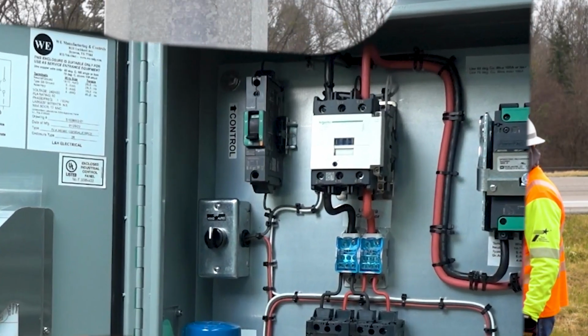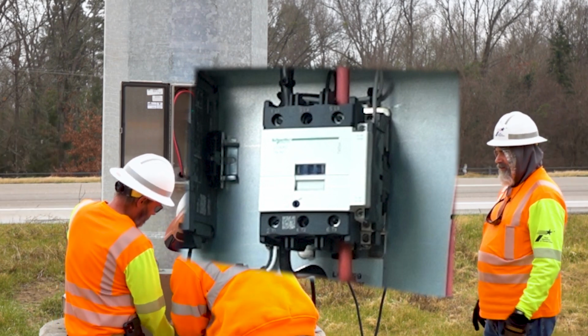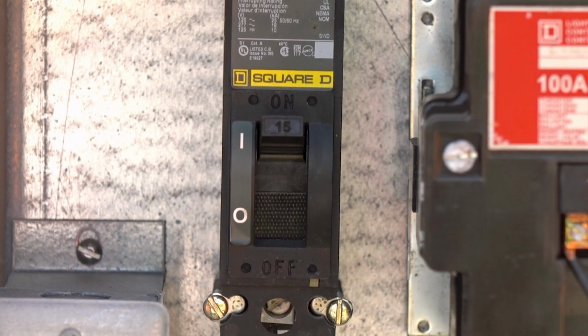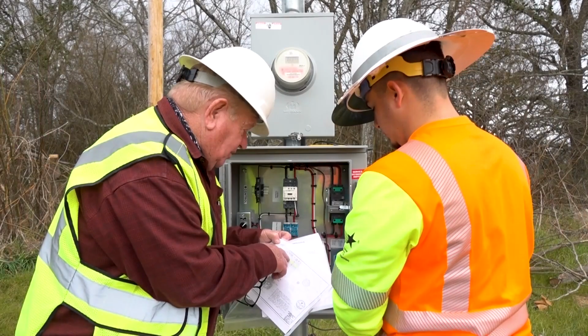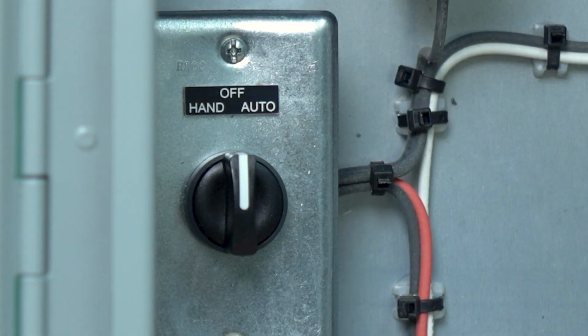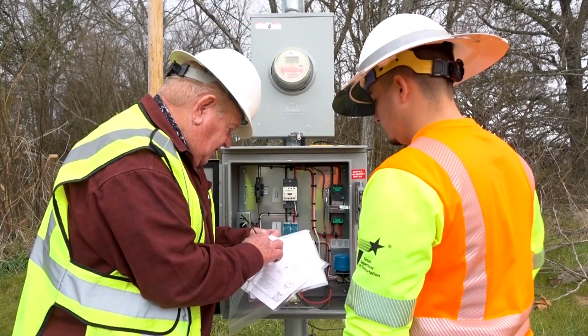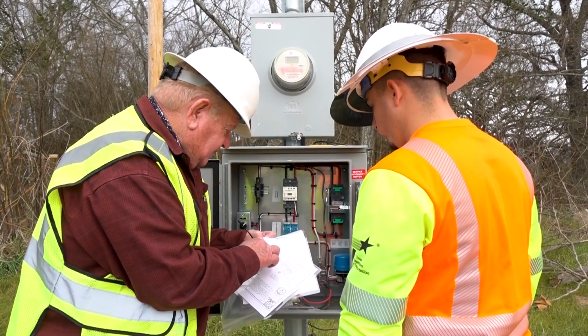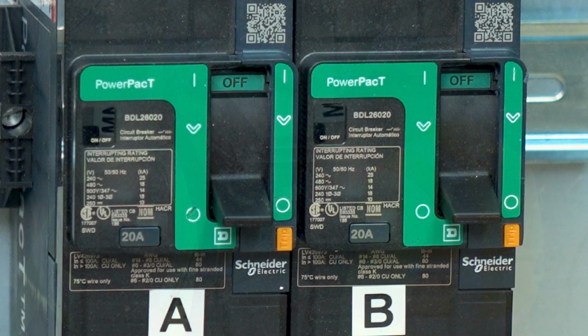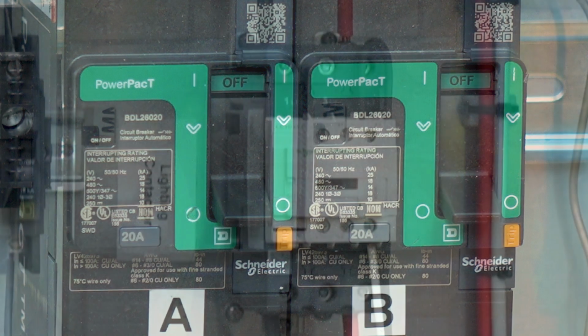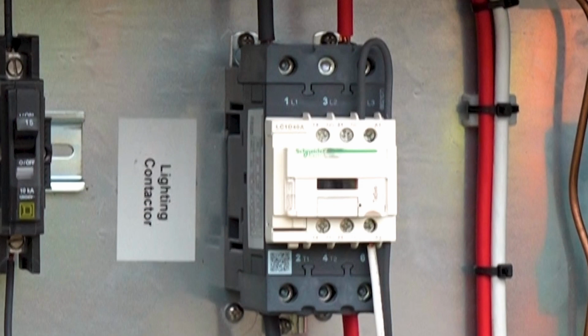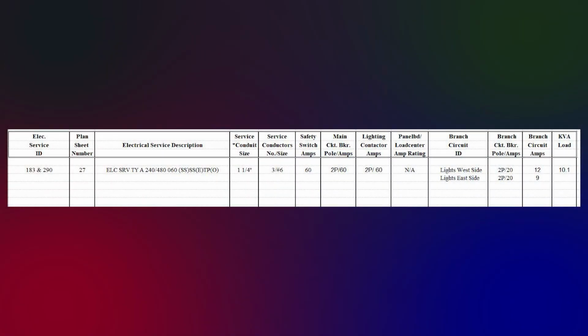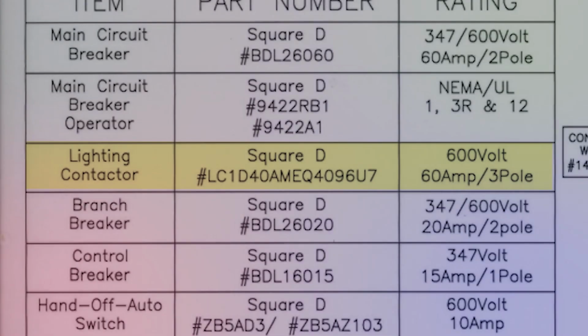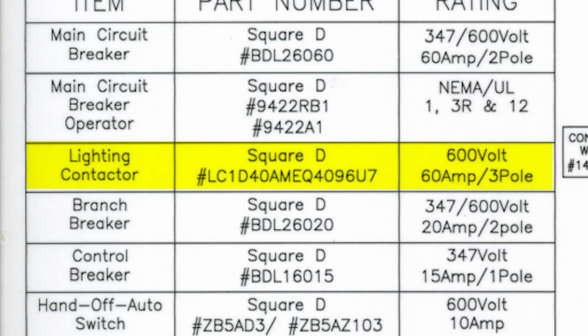The lighting contactor switches the power on and off from the load side of the main circuit breaker to the branch circuit breakers. A control circuit controls the lighting contactor. The lighting contactor's coil is fed power from the hand-off-auto control circuit. When the coil is energized, the lighting contactor turns on and powers the branch breakers. The branch circuit breakers feed power to the roadway luminaires. The lighting contactor should be labeled for easy location within the panel. The ampere rating and the number of poles for the lighting contactor is shown on the electrical service data chart in the plan set. The ampere rating, brand, and model number for the contactor is on the unique line drawings sent with the enclosure by the UL 508 shop.